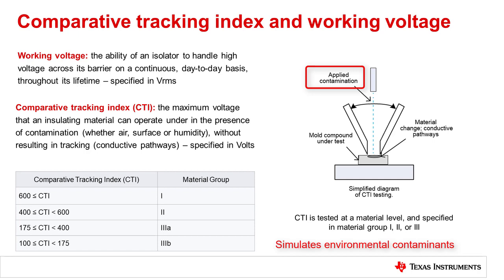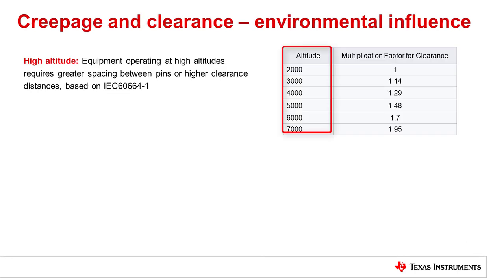Environmental conditions will also influence minimum creepage and clearance distances, with dependence on the end equipment use case, altitude, and environmental pollution degree. At higher altitudes of 2,000 to 5,000 meters above sea level, the air pressure is lower, causing peak overvoltages such as surge or temporary overvoltage to more readily cause arcing between isolator pins.